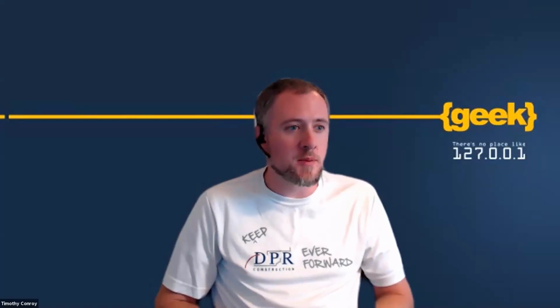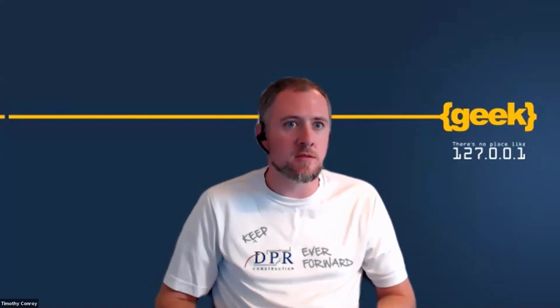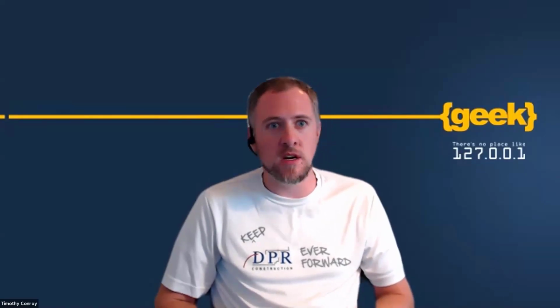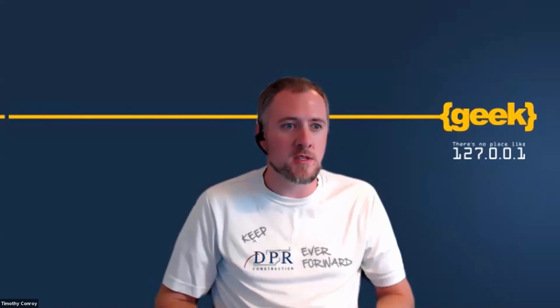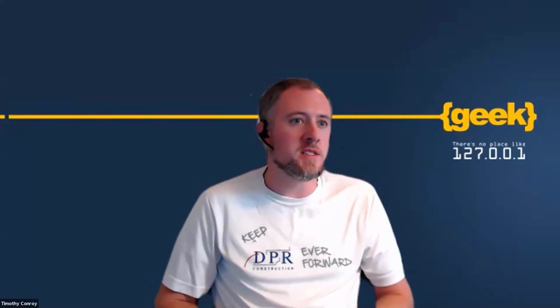I see some coworkers on this call, so I'll pull from a lesson learned they shared that solidified this use case for a client we're both working for. They were doing 4-inch stub-ups in the data hall of a massive facility, about 500,000 square feet per building. Through scanning, they realized the stub-ups were 4 feet off. The person who did the layout came off the wrong column line, which is understandable—they pulled from the column line the dimension that was supposed to be, and spray-painted a dot marking where the rack should sit. Through scanning, we caught that before the slab was poured. If we hadn't, it would have easily been a $100,000 mistake.